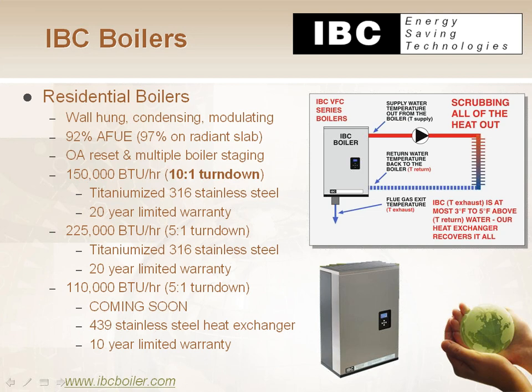It's high efficiency. It's condensing. It's modulating. It has a titaniumized stainless steel heat exchanger, which means that we can get some longer warranties with it. The residential ones have a 20-year limited warranty on them. But there's 2 reasons why we like to use this boiler a lot that he does different than some of the other boilers that we have available to us.